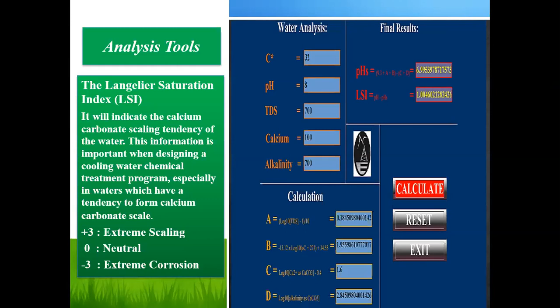So here is a live example of what we did, a calculation based on that. TDS was 2000, pH of the incoming water was 8.2, C is nothing but the temperature, calcium was 200, alkalinity was 450. Based on that, we calculated the LSI, or Langelier saturation index, of that water to be near about 1.26 or 1.3, right? After that, we installed the EST, and I will show you the parameters I got.